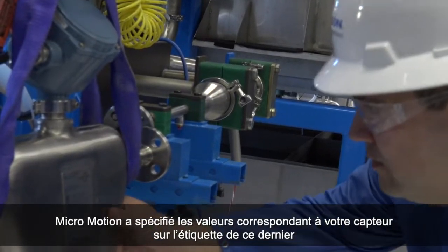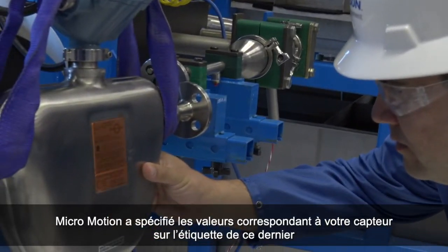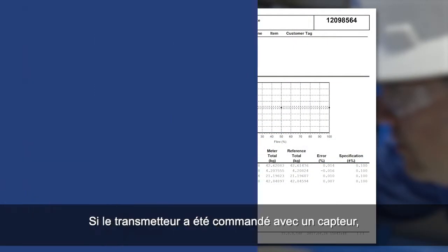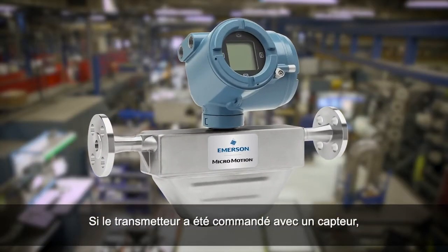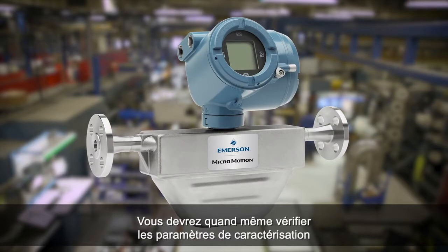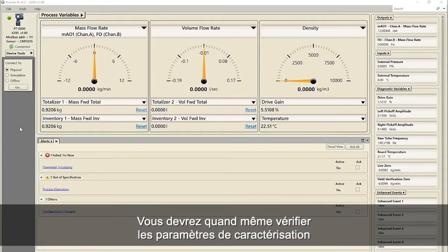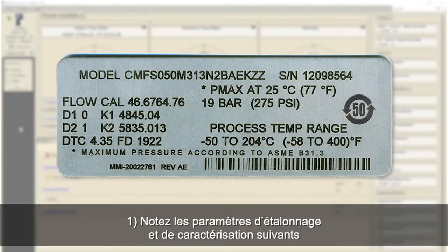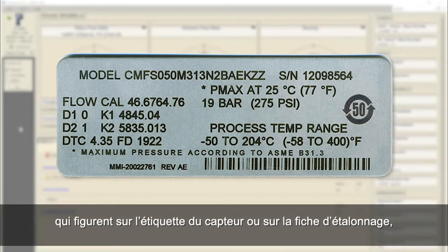Values for your sensor are provided by Micro Motion on the sensor tag or the calibration certificate. If your transmitter was ordered with a sensor, it was characterized at the factory. However, you should still verify the characterization parameters. First, record the following calibration and characterization parameters from the sensor tag or calibration sheet.